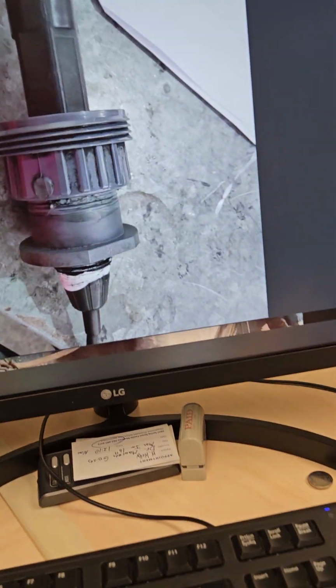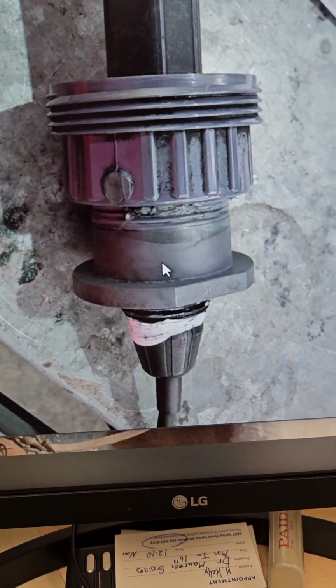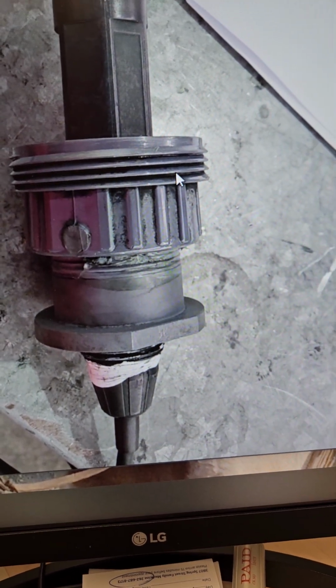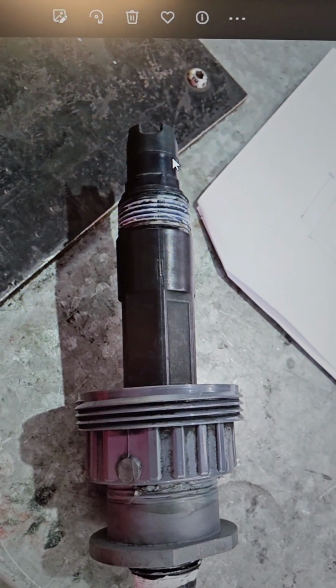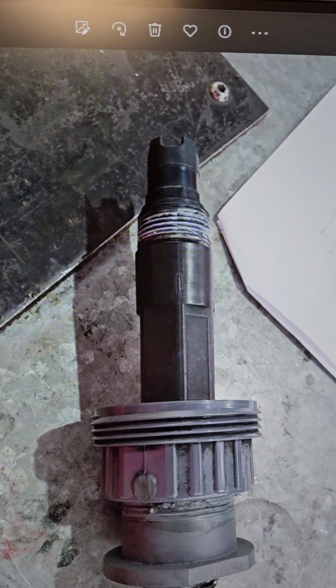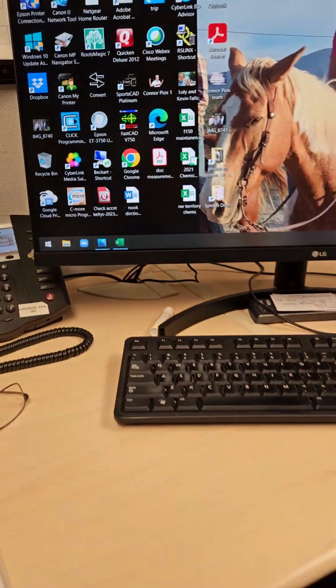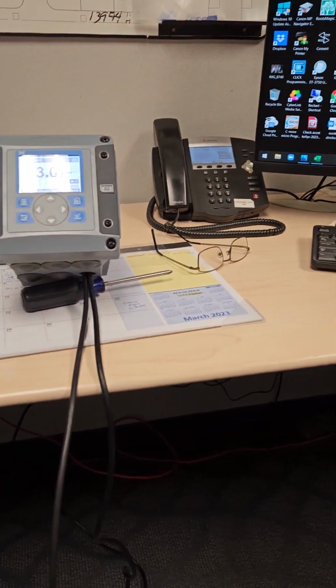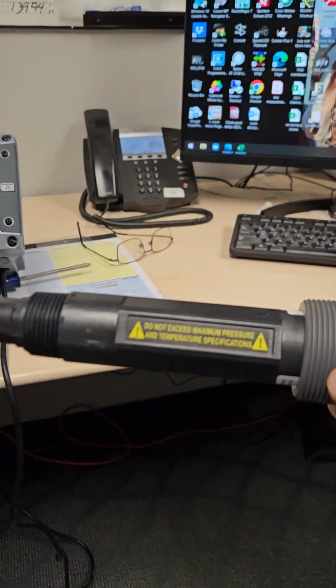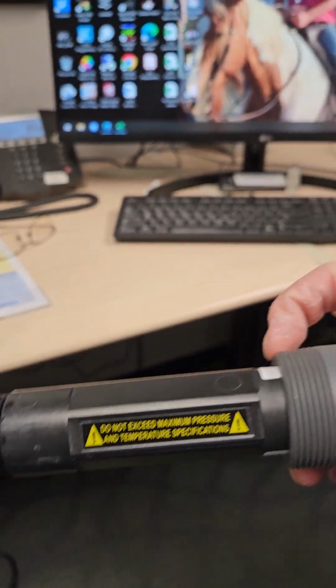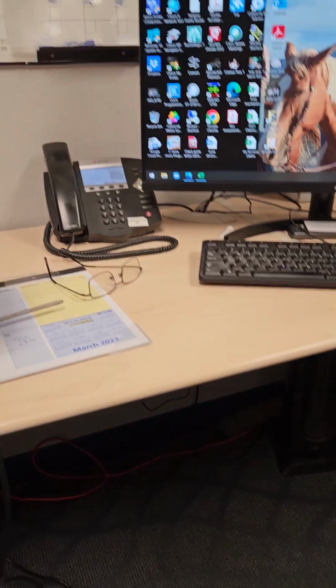Again, it looks like this when the adapter is threaded in properly to the union, so then the union coupling can come off, and the probe down at the end can get a good reading. So a lot of our probes have changed over the years. That's what the adapter is for, when you have a 1 inch probe and you have an old 1.5 inch trap like you just saw with the unions.